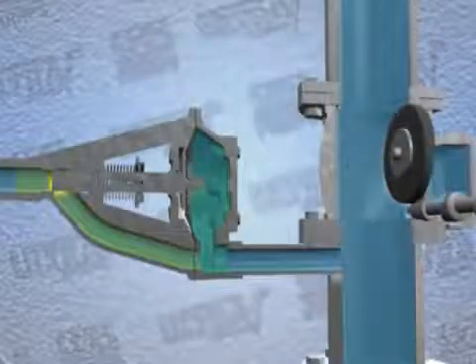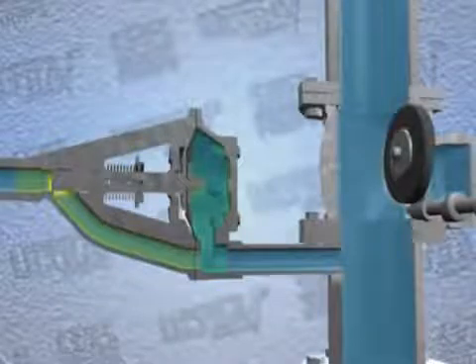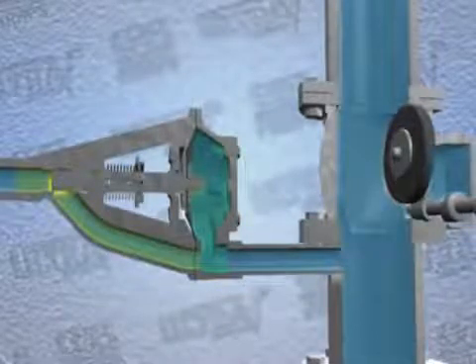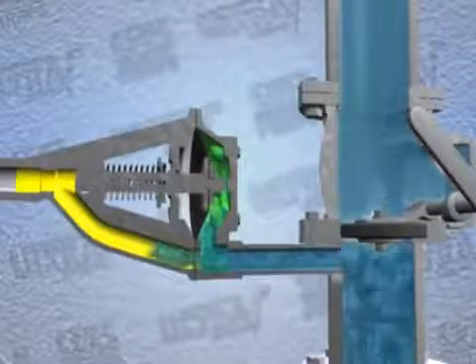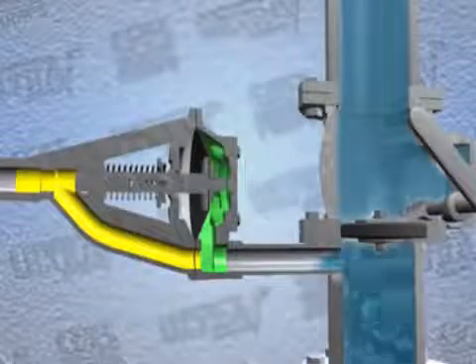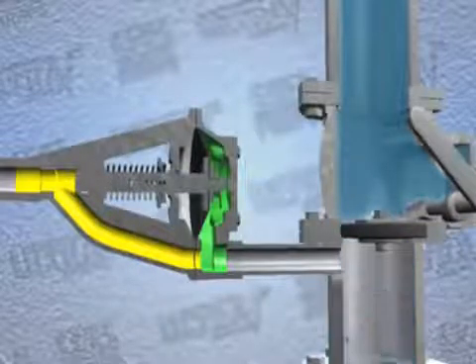Once closed, the discharge pressure from the pump opens the check valve and the pump is in full dynamic operation. At the end of the priming cycle when the pump shuts off, the discharge check valve will close due to static discharge head in the piping, and then the air release valve returns to the open position.